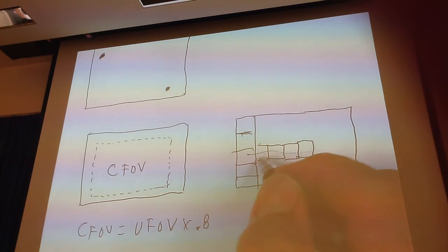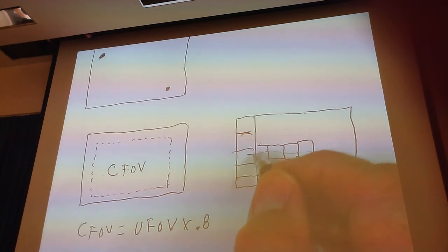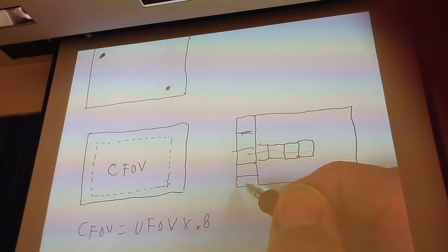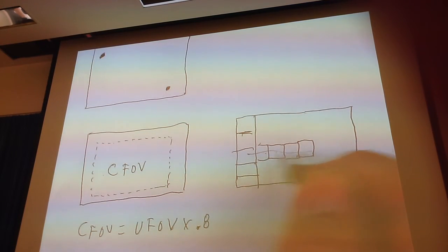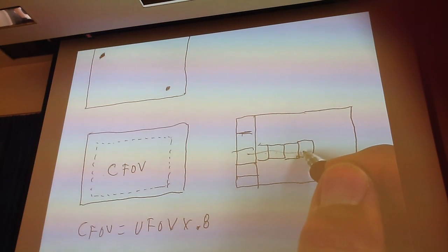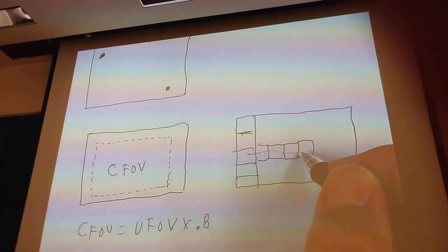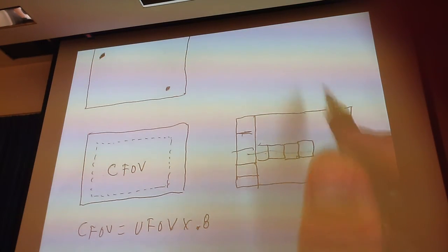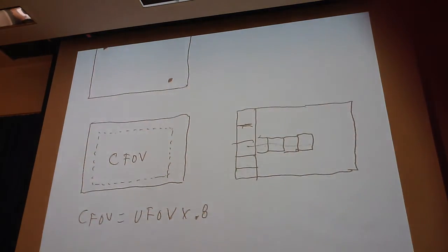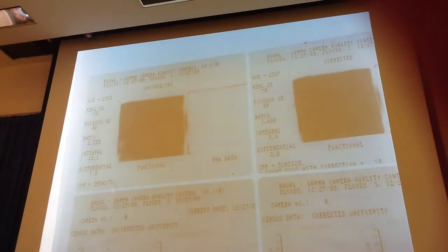So basically, this is a little bit more sensitive way of determining if there's non-uniformity or if there are uniformity problems. Okay? Does that make sense? So, in this particular thing here, because we're going to be starting to talk a little bit about SPECT quality control now. Okay.